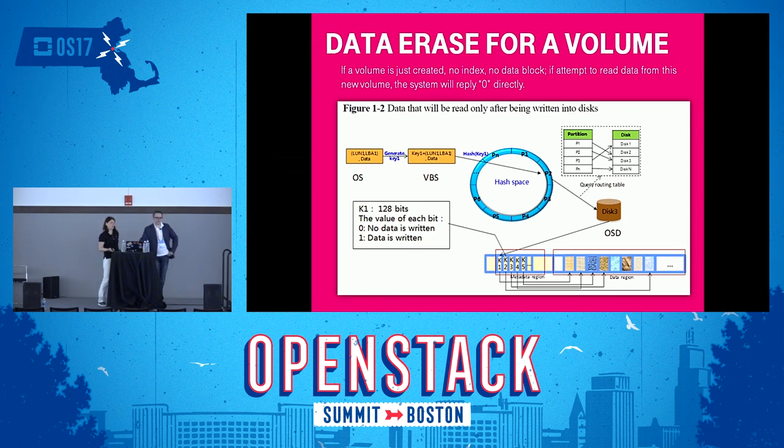So if we are decommissioning servers, there's a big shredder where all hard disks, all flash components, whatever, are destroyed before they are leaving the data center. So there's one way in and no way out. So even not to lose data by transporting servers or whatever, if it is in the data center and if it had customer data on it, it won't leave the data center in a secure way. Or if it's broken, we get a replacement part by the supplier and the disk that we are using will be destroyed afterwards.